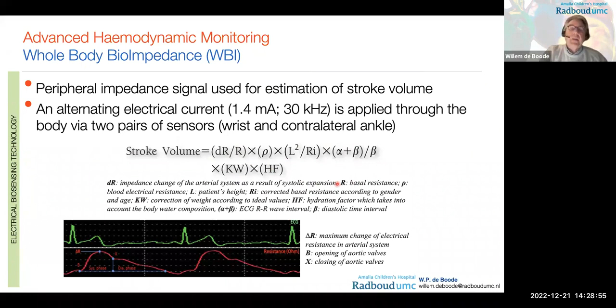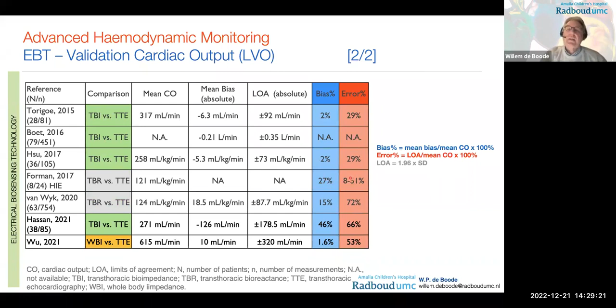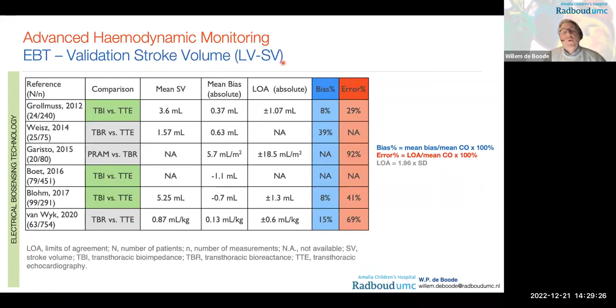So it's not only located on the thorax, but it's a peripheral impedance signal. You have the current applied through the body via two pairs of sensors, one on the wrist and one on the contralateral ankle, and with some kind of correcting factors, unknown factors, they derive stroke volume via the change in impedance. Let's look at the validation studies. What you can see is transthoracic bioimpedance, transthoracic bioreactance, and you can see that the error percentages do change a lot. Also in this slide, you can see most of them are really over the 30% accepted for a clinical application. Also, if you look at stroke volume instead of cardiac output, it's a rather high error percentage.